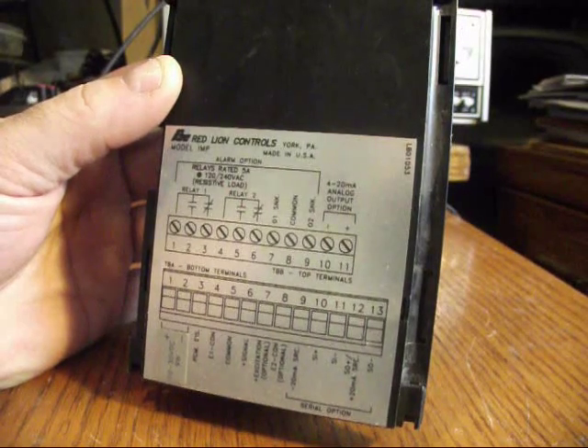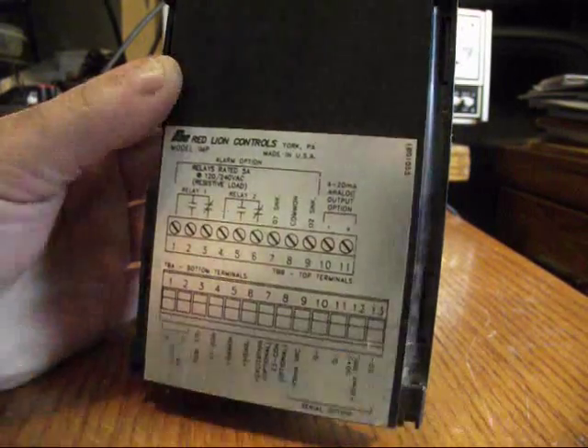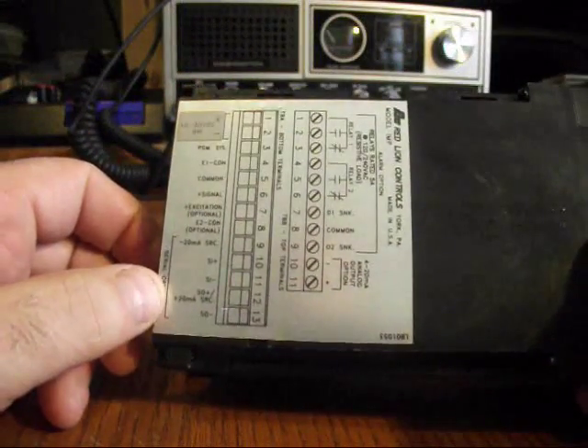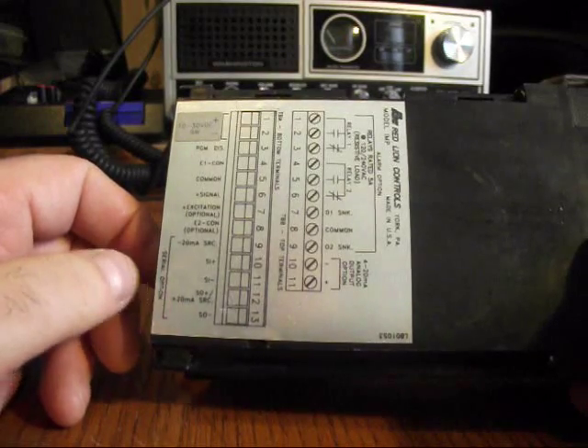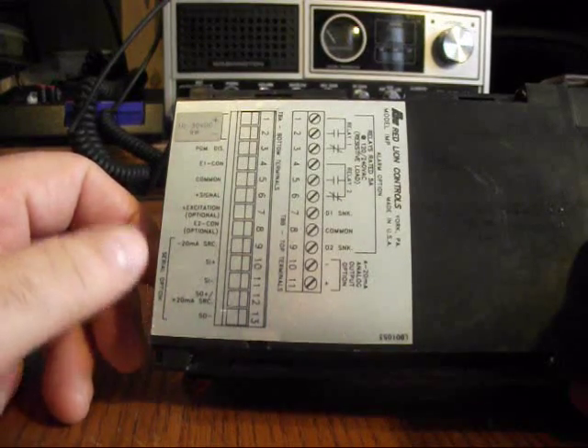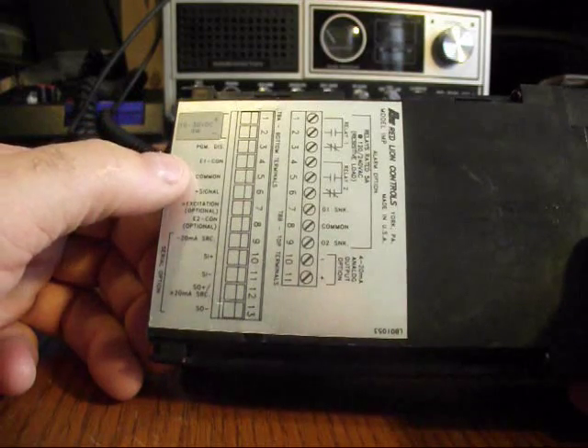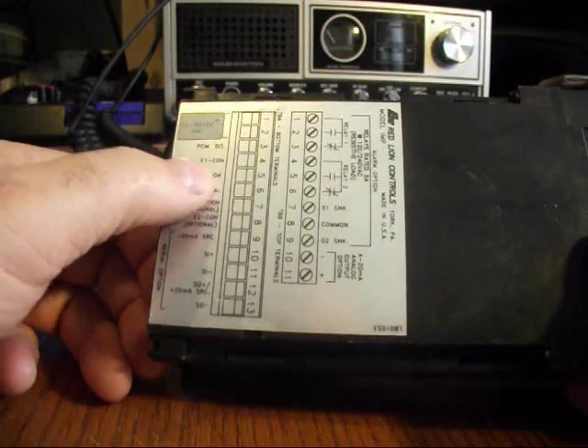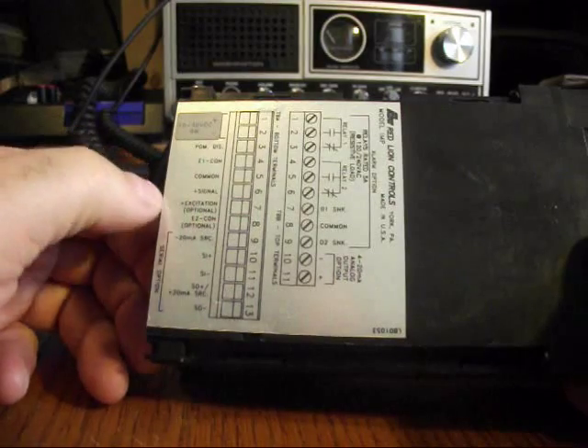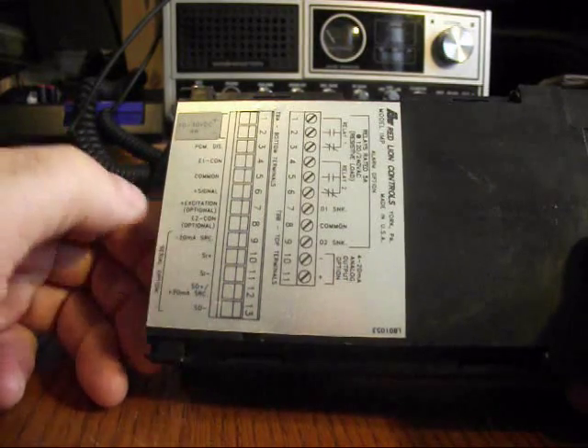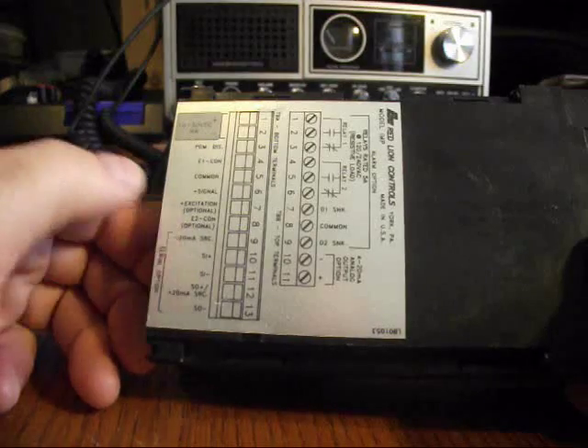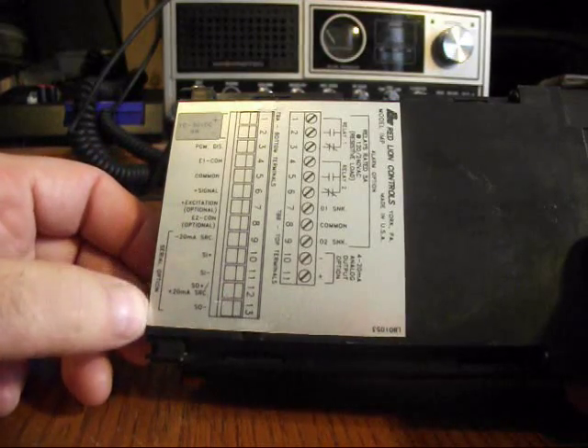And terminals, and if you look here, it says 10 to 30 volts DC plus minus. I had this powered up and it said UL, which means under range, which means there's no signal going into it. There's program, DIS, E1 COM common, signal plus, excitation optional, E2-CON optional, minus 20 milliamp SRC, and so on, the whole nine yards.